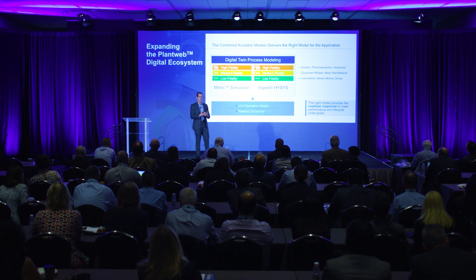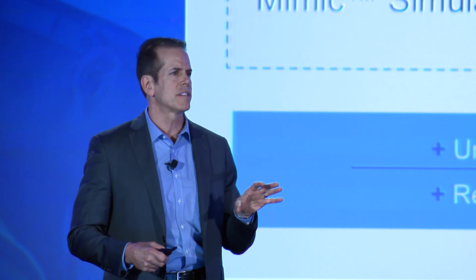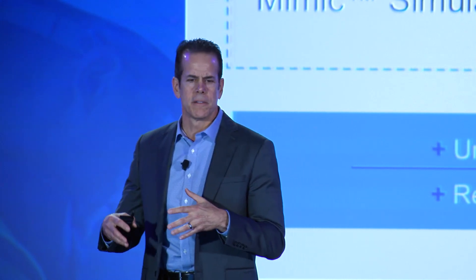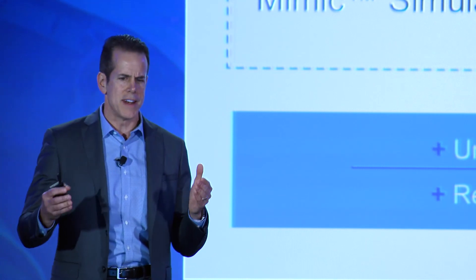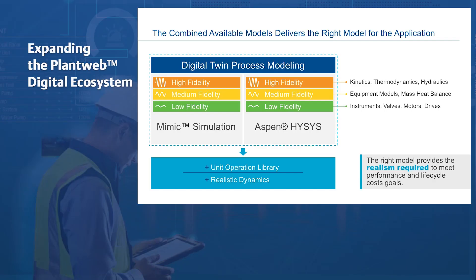Combining Mimic simulation and Aspen HYSYS with the Mimic HYSYS Link allows our users to have the right model for the application and the process. Through the course of a project or the lifecycle of a plant, different complexity or fidelity of process models support different uses. Accurate models of motors, drives, valves, and instruments are essential for interlock verification and testing regulatory controls. Mass and heat balance models are required for validating sequences and phases of a batch. And reaction kinetics, advanced thermodynamics, plant piping, and hydraulic models are necessary to develop in-depth operator knowledge and make significant operational improvements. Mimic and HYSYS together provide the right models for the real-time dynamic performance required to support top quartile operational performance.